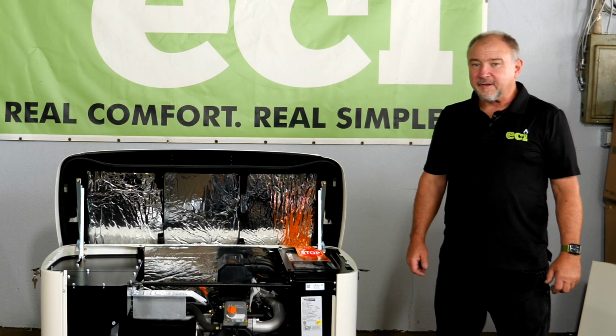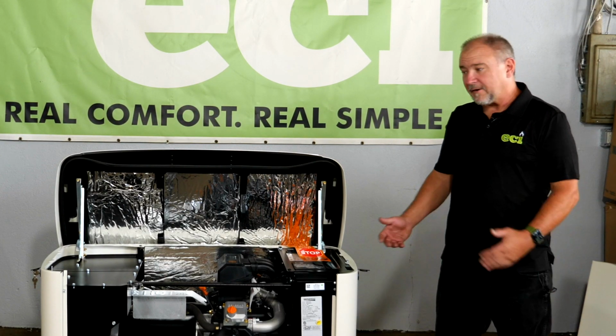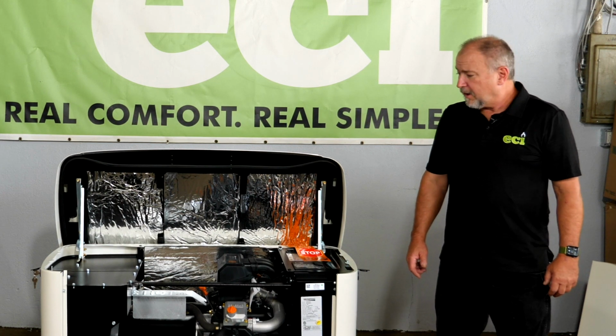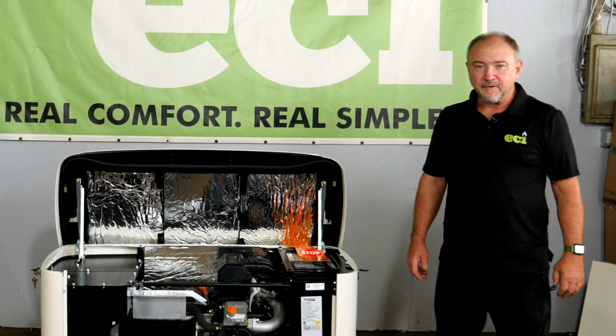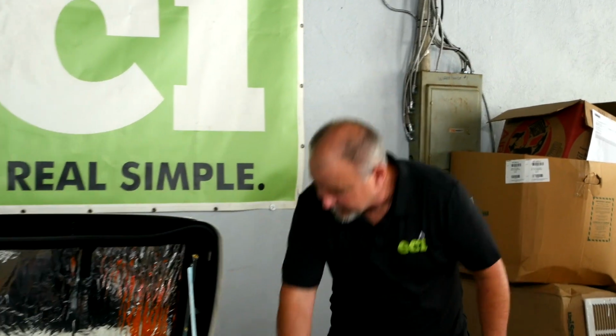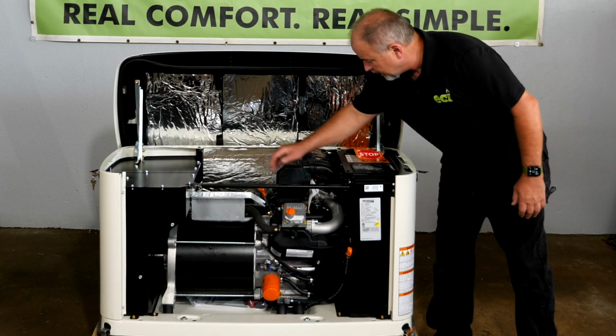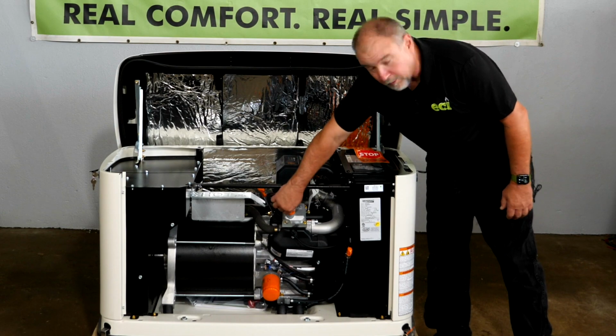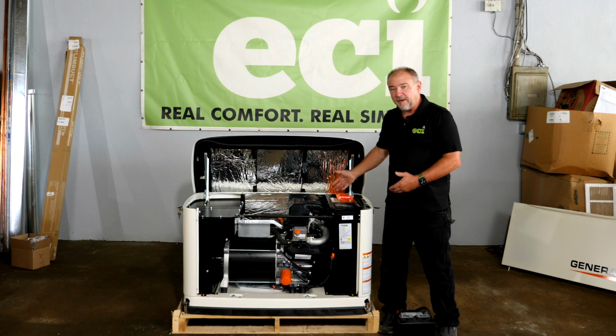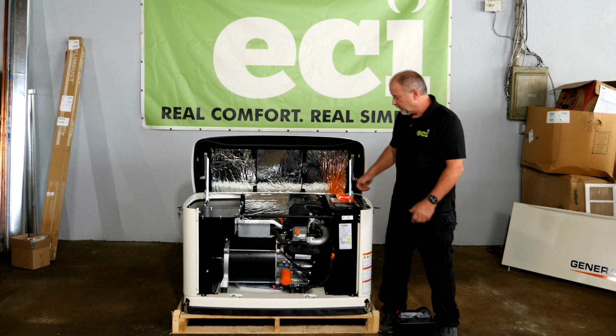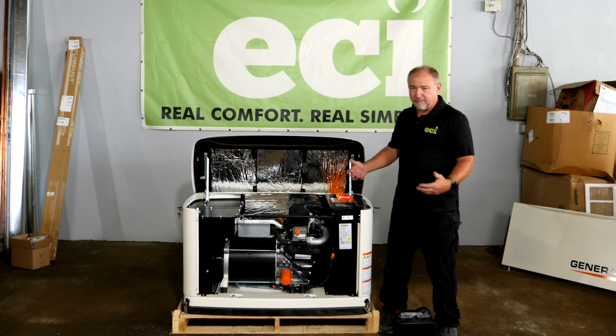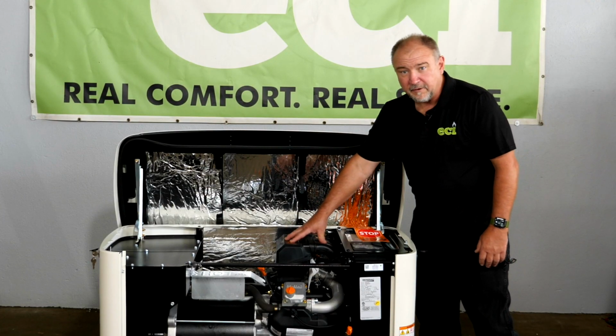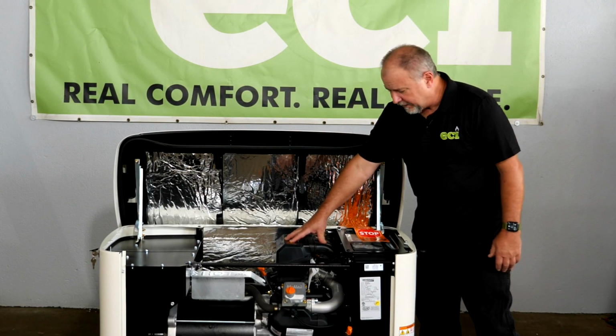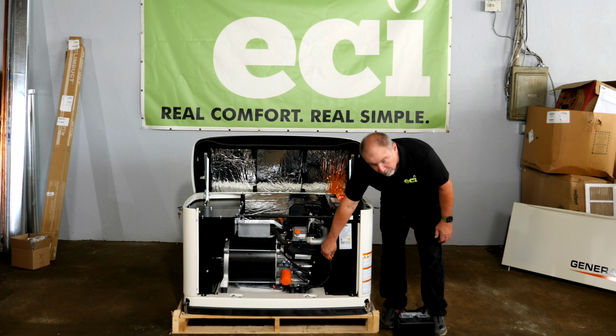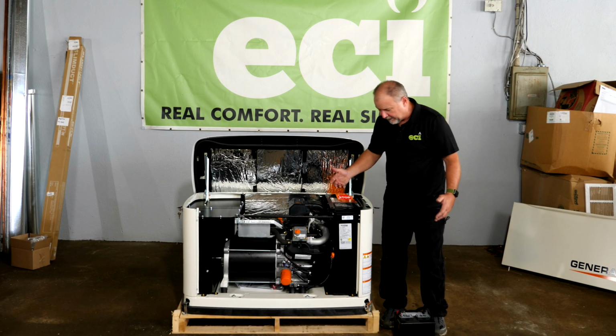Part of the services we offer at ECI includes not just installing the generator, but the required maintenance afterward—like the yearly oil change. Here's the oil filter and dipstick; this is where we add the oil. We check the valve clearances as required, change the spark plugs every couple of years, and check and replace the air filter as needed. This is also how we drain the oil out of the engine.